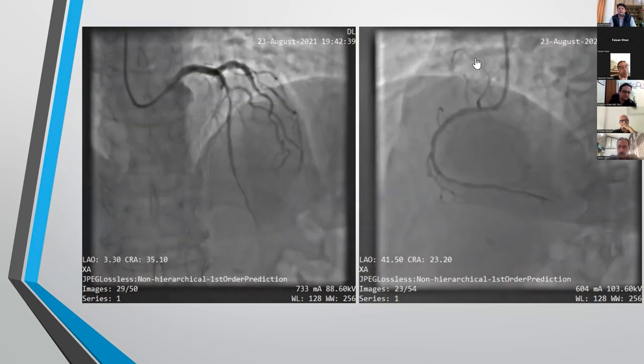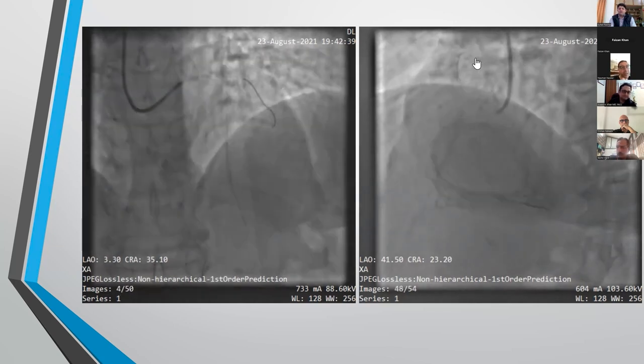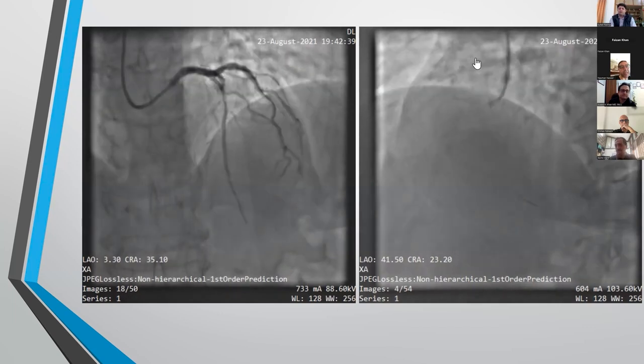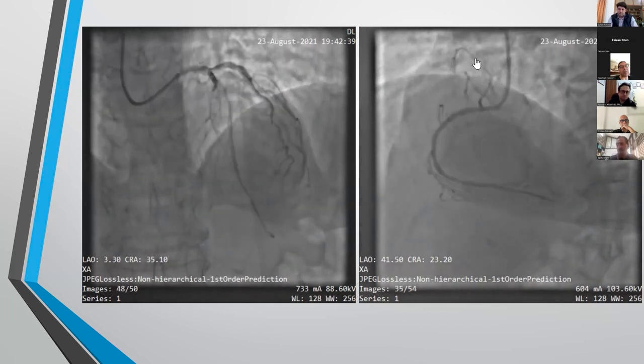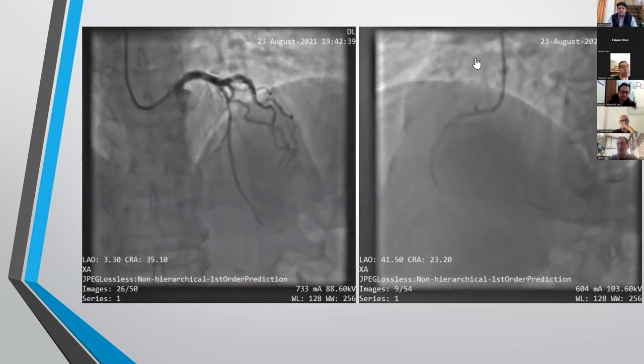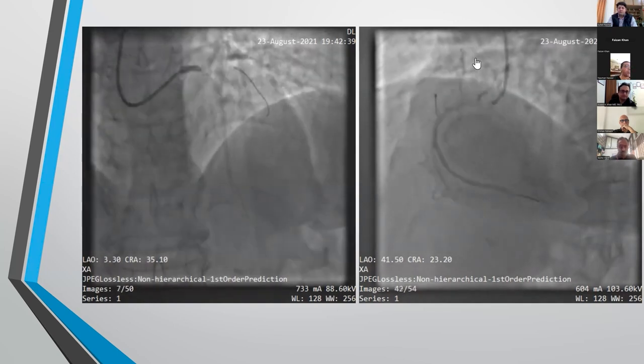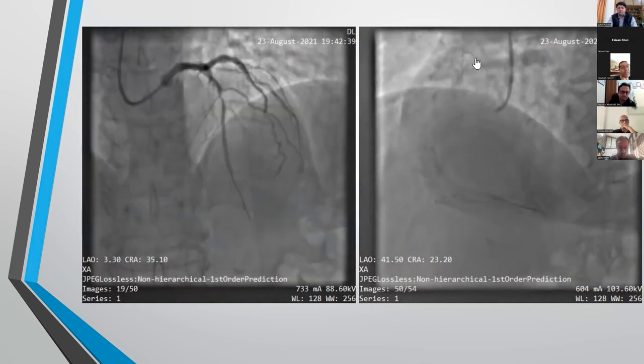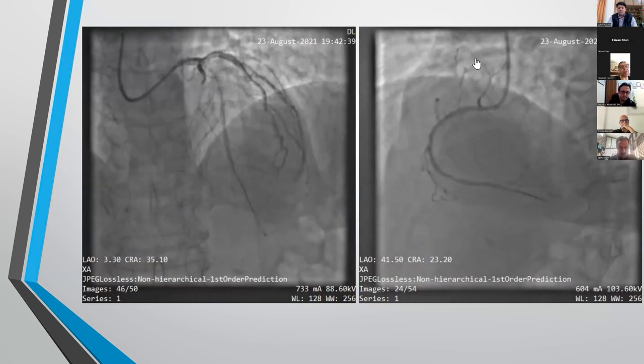दूसरा, a lot of times you have to watch for drift whenever you do an FFR recording: pull the wire back, जो प्रेशर ट्रांसड्यूसर का है, up to the guide catheter tip and make sure the pressures are still equalized, and the drift has not taken place.